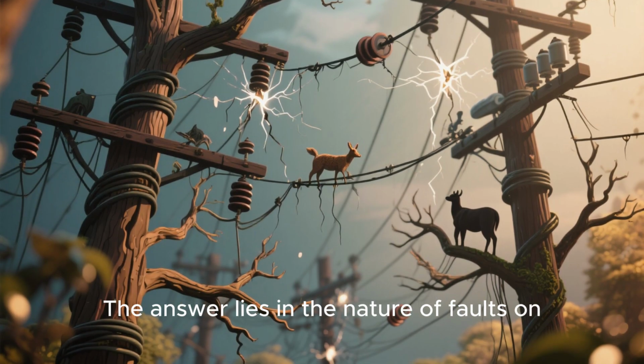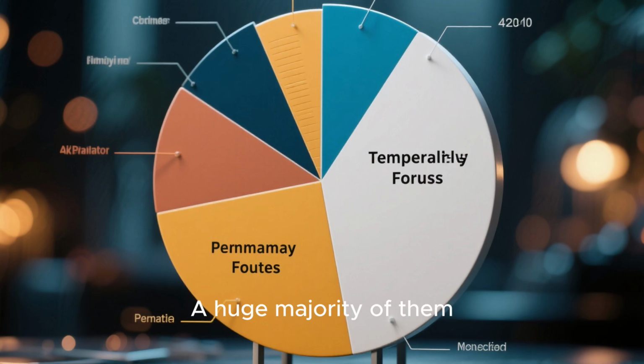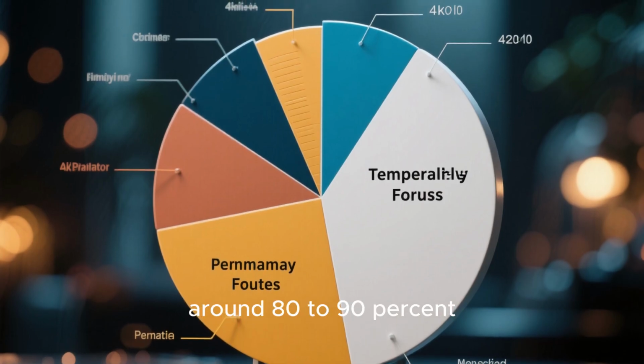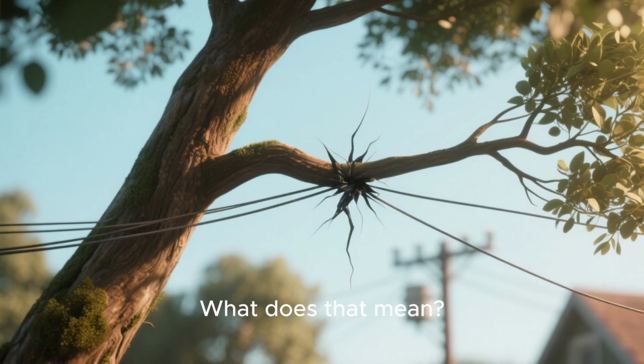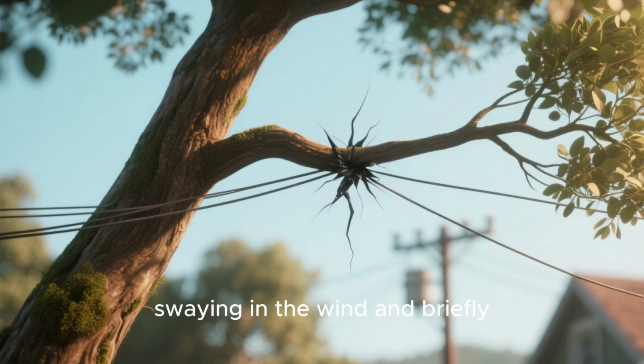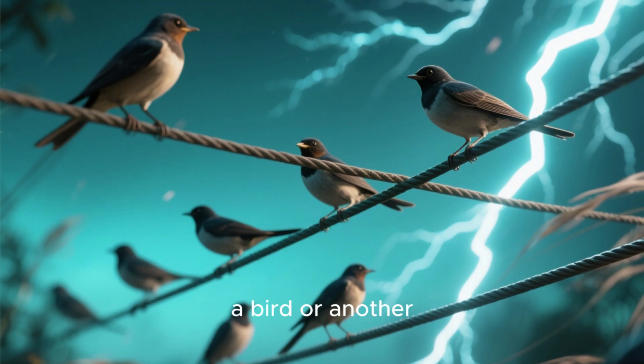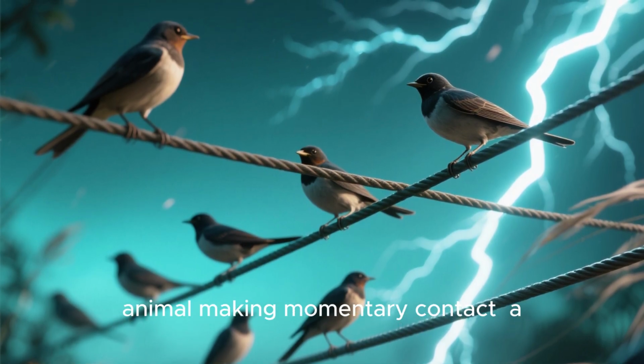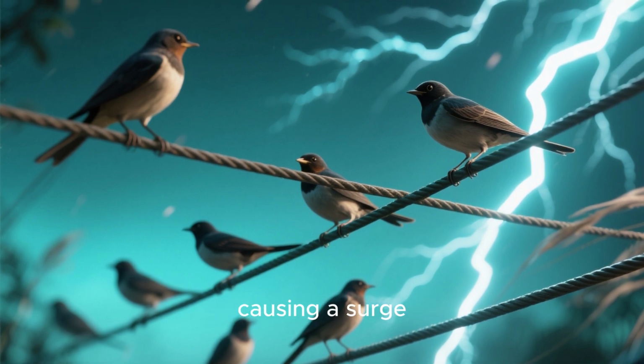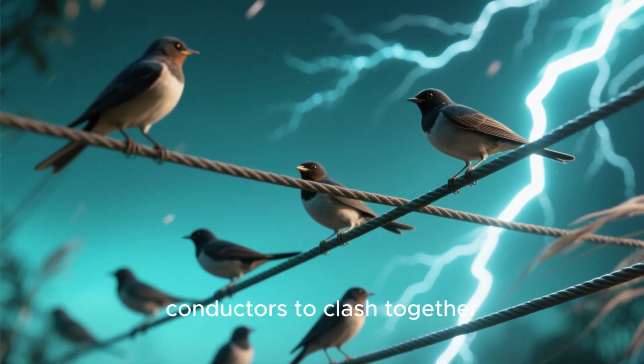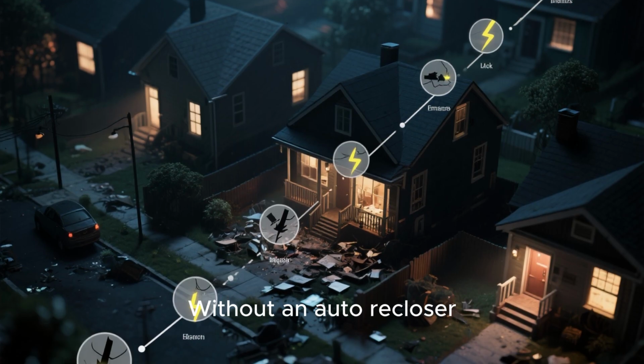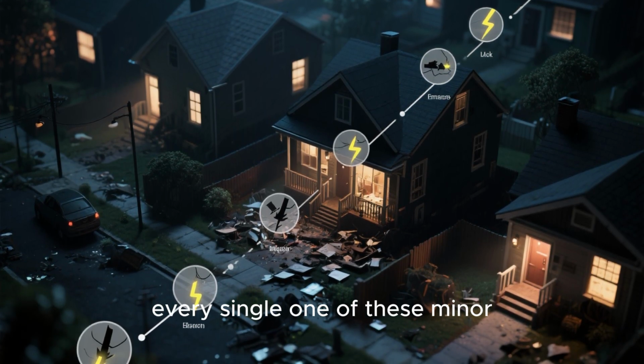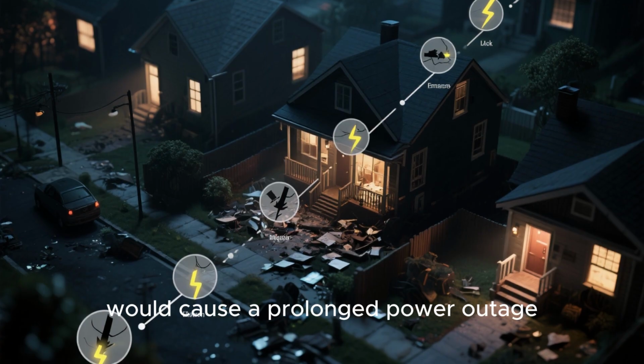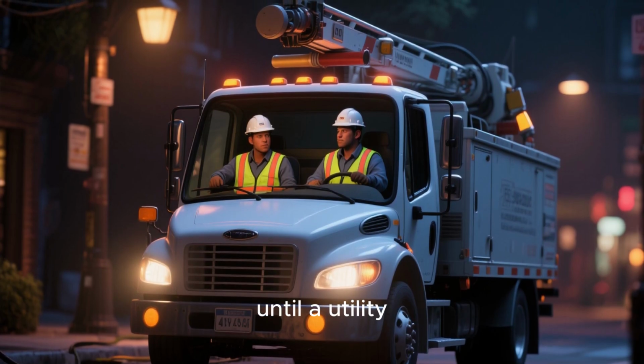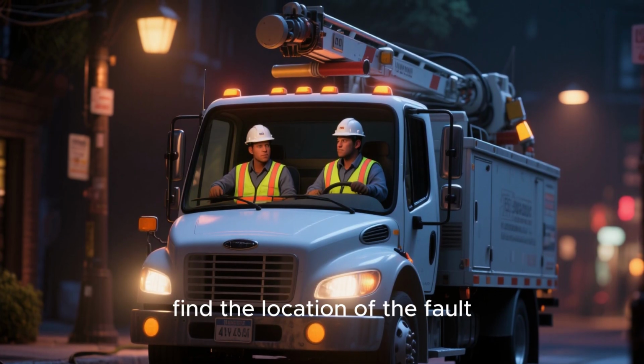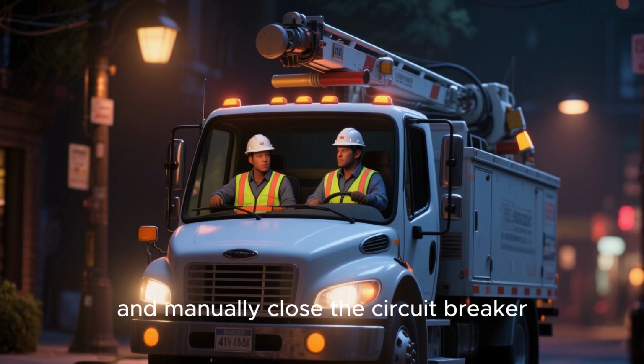The answer lies in the nature of faults on overhead power lines. A huge majority of them, around 80 to 90%, are temporary. What does that mean? It could be a tree branch swaying in the wind and briefly touching a line, a bird or another animal making momentary contact, a lightning strike nearby causing a surge, or even strong winds causing the conductors to clash together. Without an auto recloser, every single one of these minor, temporary incidents would cause a prolonged power outage. The power would stay off until a utility crew could drive out, find the location of the fault, and manually close the circuit breaker.